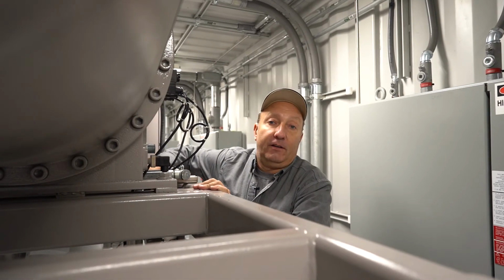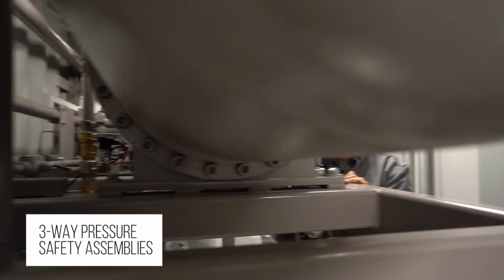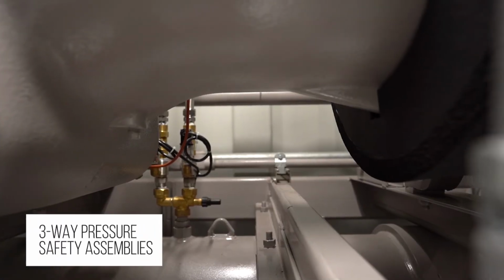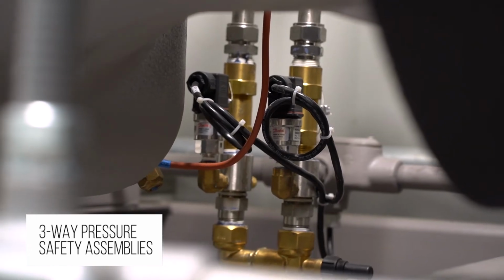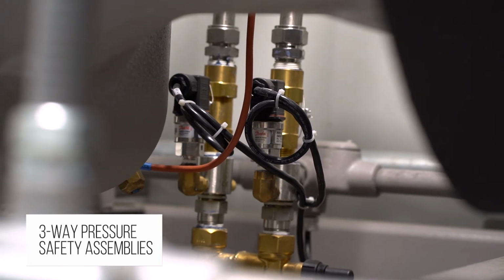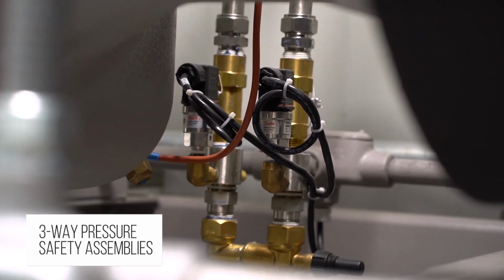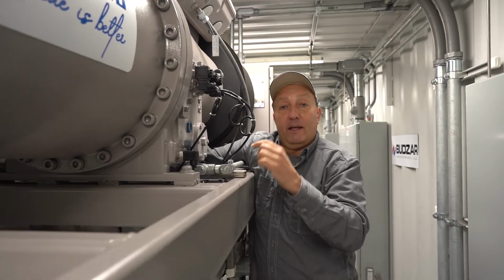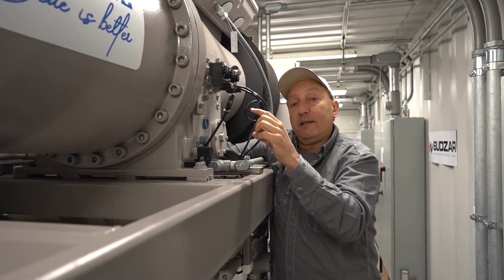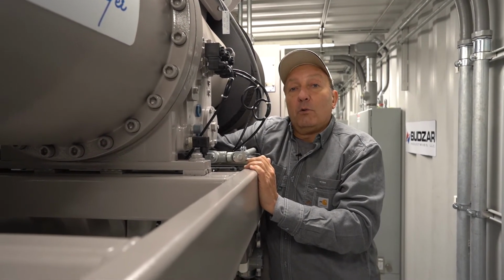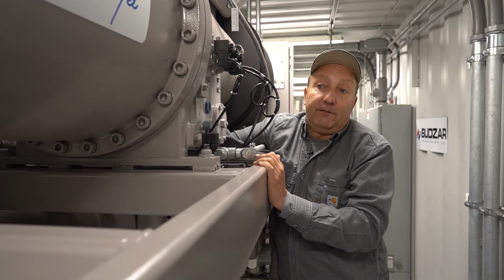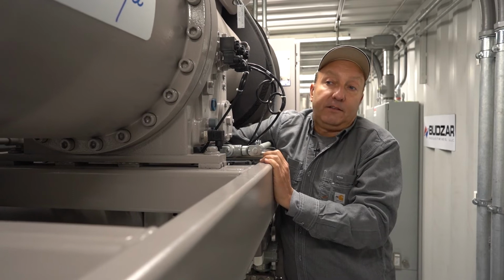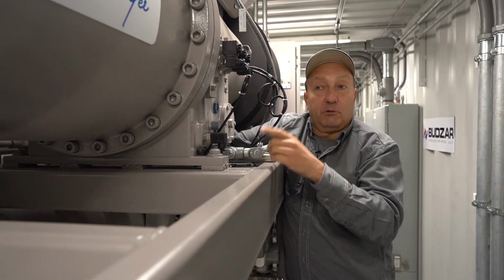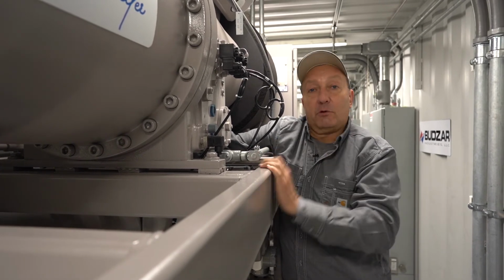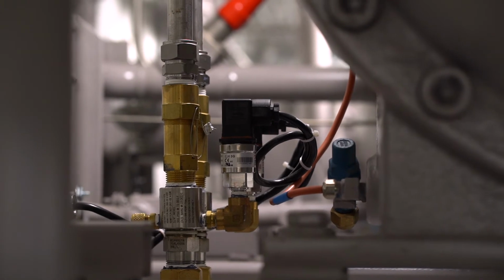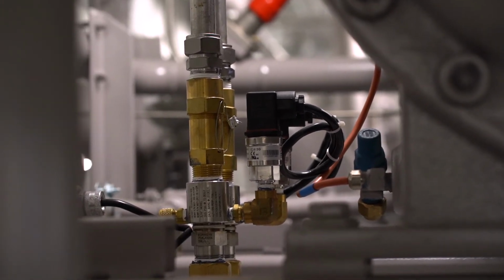Okay, one of the key features of our refrigerant circuit is our three-way pressure safety assemblies. We have a three-way valve where one connection is connected to the refrigerant circuit, and then we have a valve where we can isolate each pressure safety valve. Each pressure safety valve also has a rupture disc, then a pressure transmitter chamber, and then the PSV. The reason for this is we want to know if the pressure increases before the safety valve releases or pops. So in this case, if we see pressure in this chamber, we will shut down the system and you'll get an alarm at the HMI, the lights will go off, and we can address the situation before the pressure safety valve releases and we lose propane to the atmosphere.